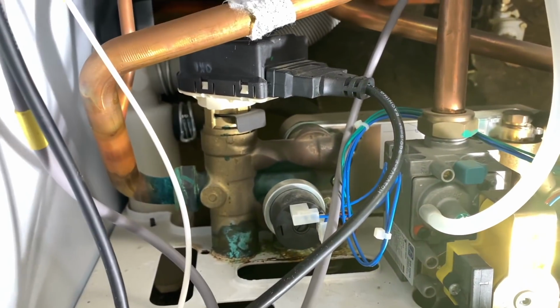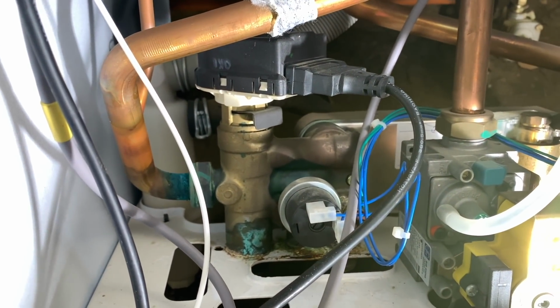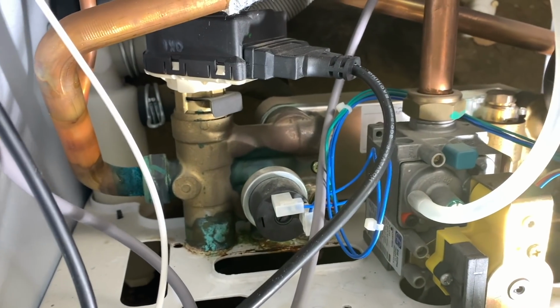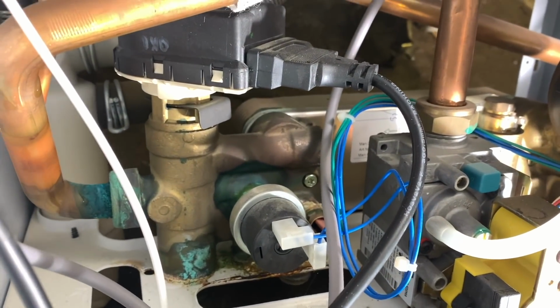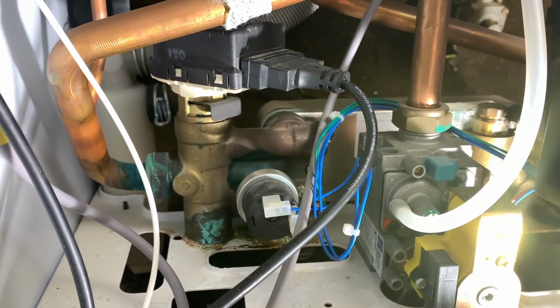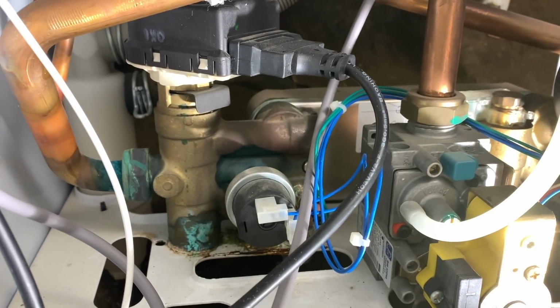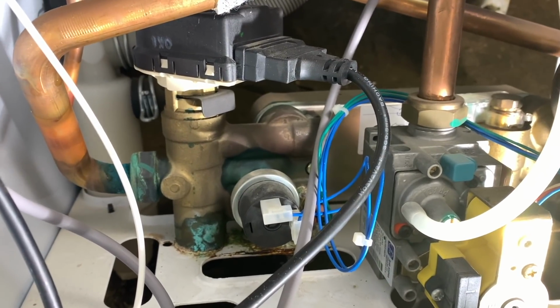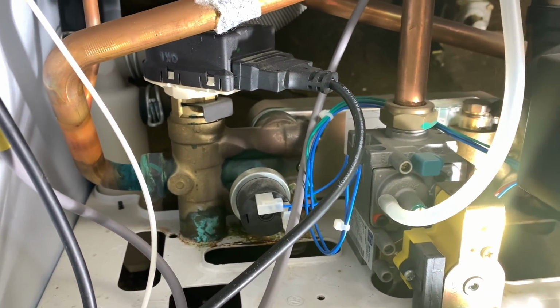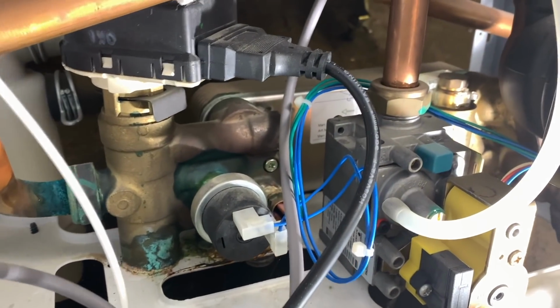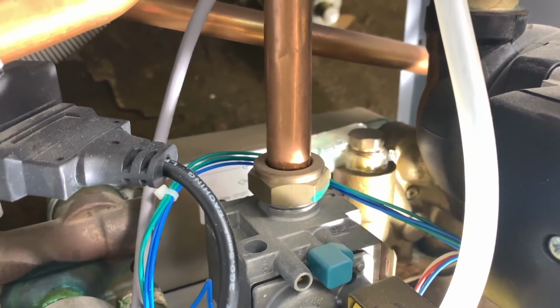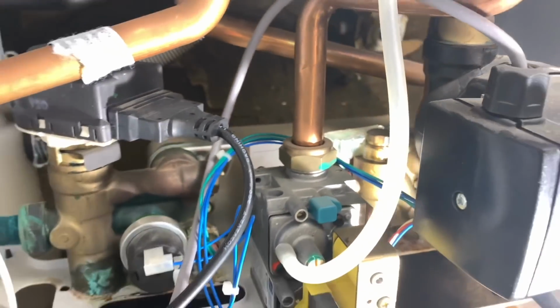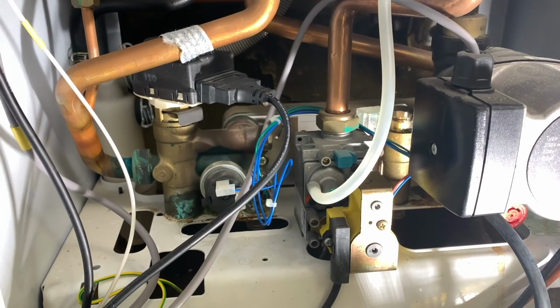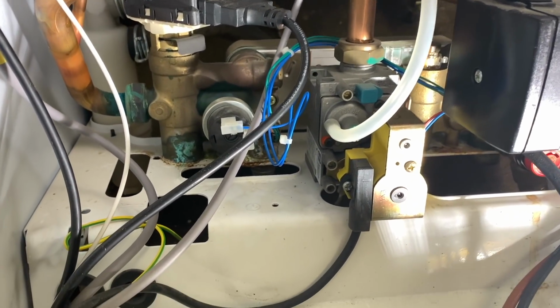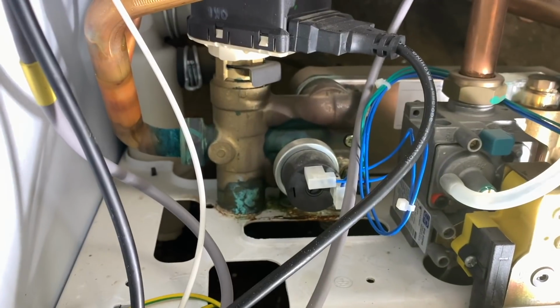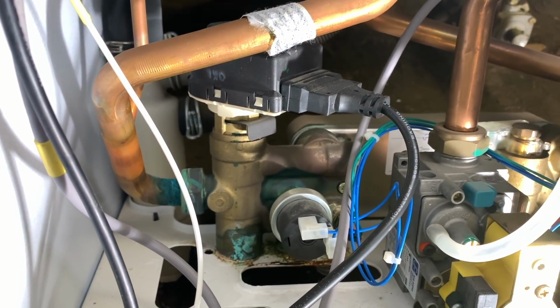You can see this is a tried and tested brass hydro block from Baxi, which a lot of engineers love rather than the composite ones, because one good thing about brass is you don't need to put those little mini shock arresters in, but you do if you're plastic and you've got a water meter or a non-return valve. So you can see even the older Baxis still have a lot of the same components because they're tried and tested and they work.